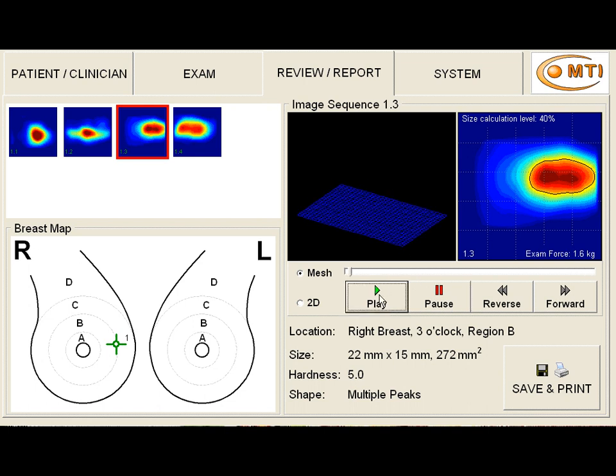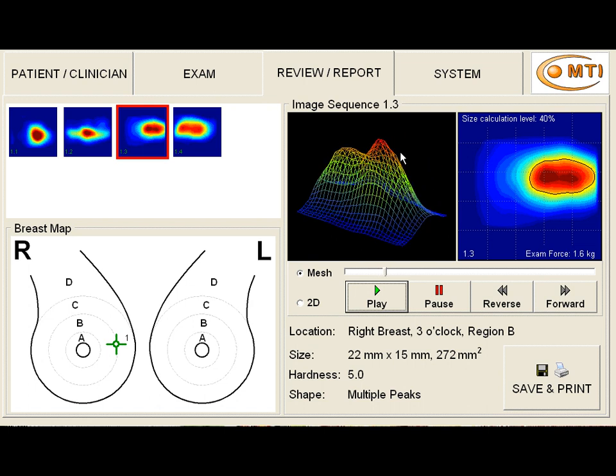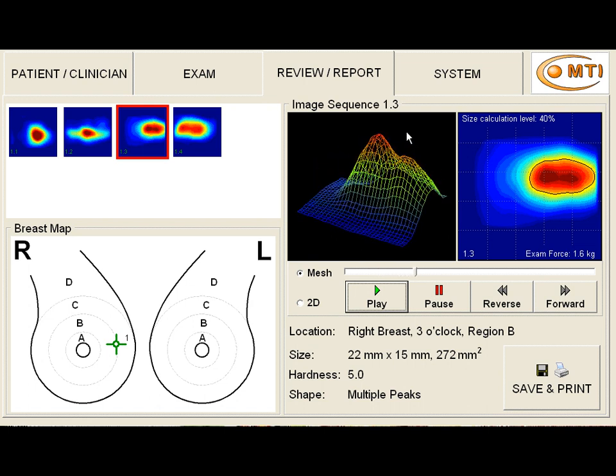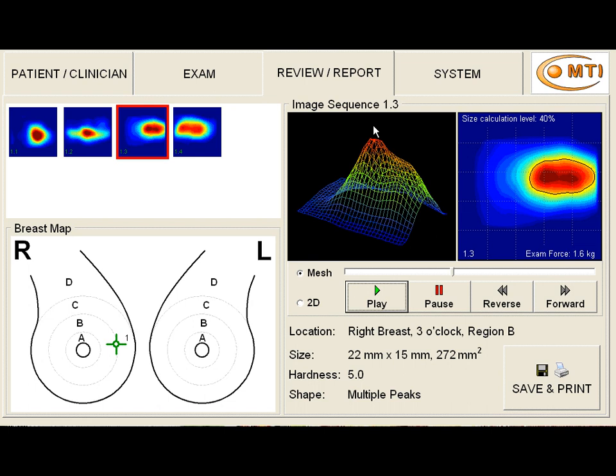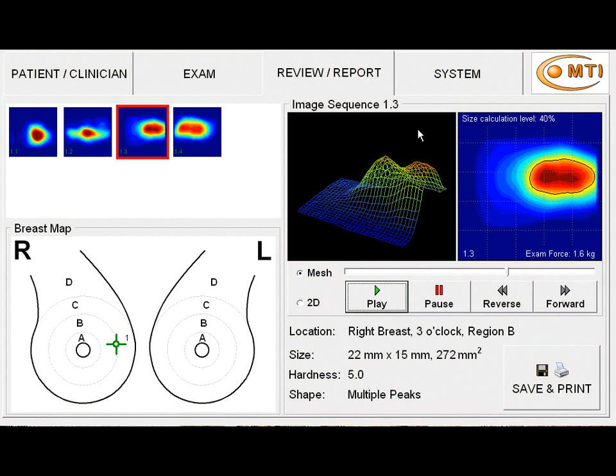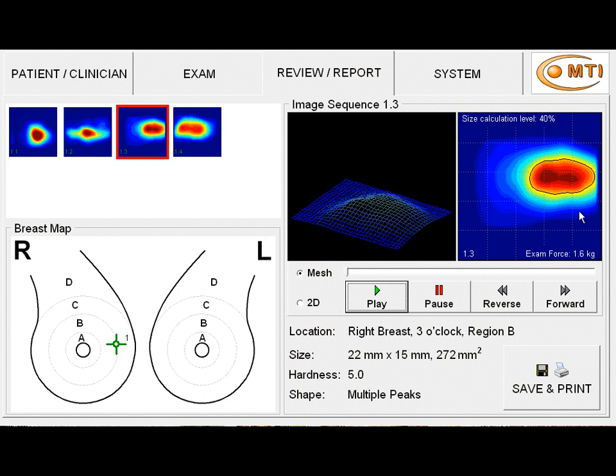Let's look at this one more time. Here the examiner is leaning a little bit more towards the left, now a little bit more towards the right, pushing more on this side of the mass, and as it goes this way, he varies. The examiner is not examining this mass with an even distribution of the transducer on top of the mass. And this is the kind of picture you get. There's nothing wrong with this type of picture. SureTouch will incorporate all that information and get an accumulated image. And what we see with the accumulated image is that there is like a double-peaked mass. There are 2 peaks, and our shape is described below here as multiple peaks. And we can see that through the accumulated image, and we can see the size of it. This gives us a very good example.